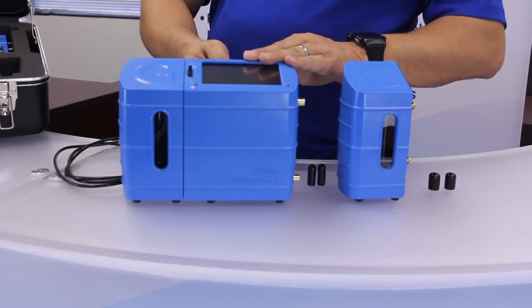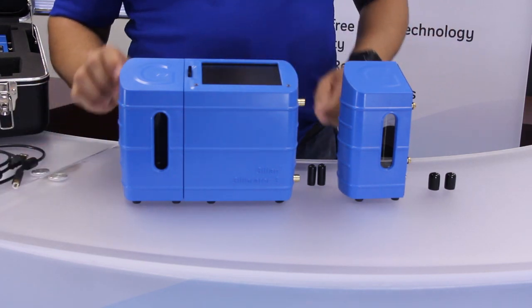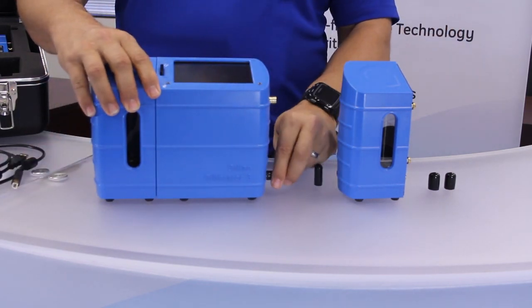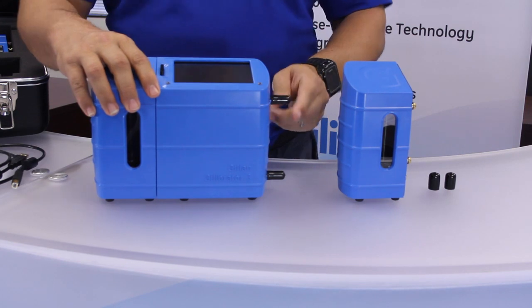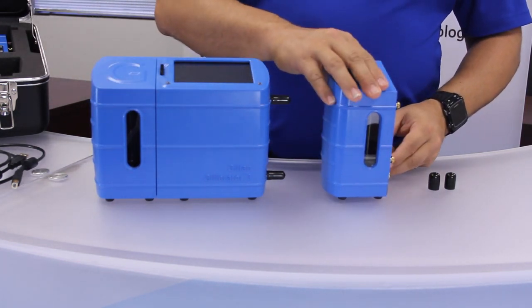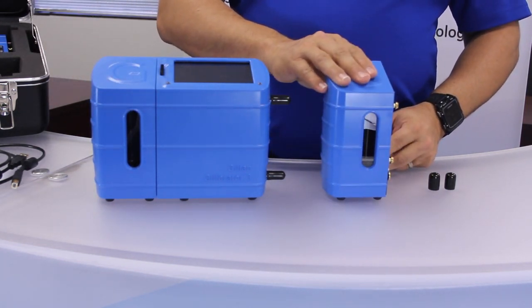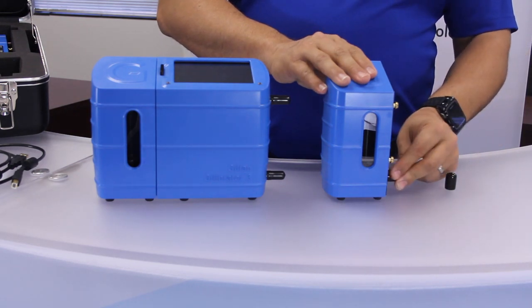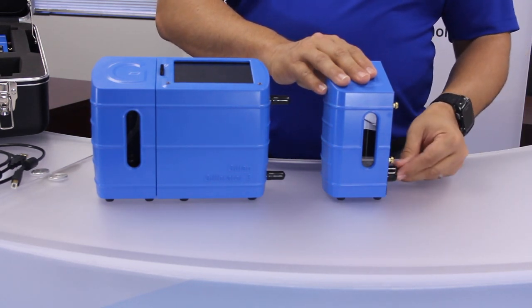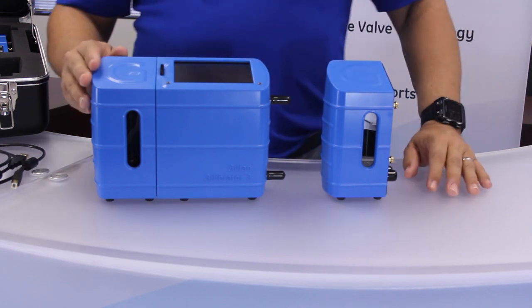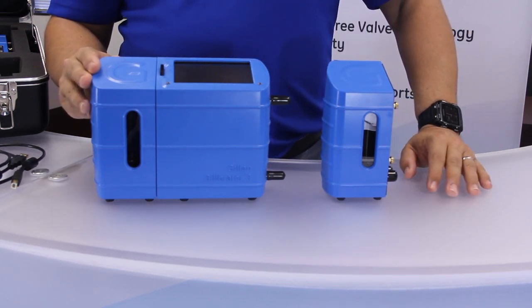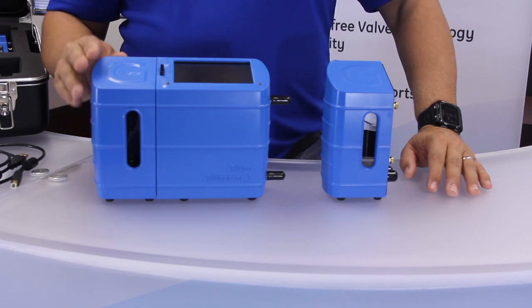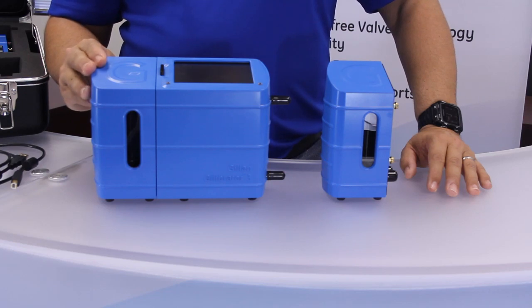Disconnect all cables from the base control unit. Place the small black caps on top of the hose barbs to the Gilibrator base. Also, if you're using a second cell, if it's disconnected, make sure you place the large black caps over the inlet and outlet ports for the cell as well. Store the unit indoors. Proper storage temperature should be between 0 and 70 degrees Celsius or 32 to 158 degrees Fahrenheit. Recharge the unit for a minimum of 3 hours prior to the next usage.